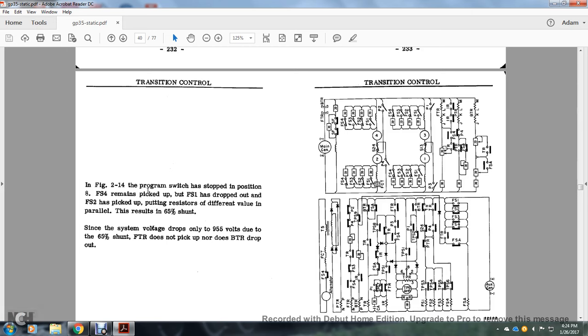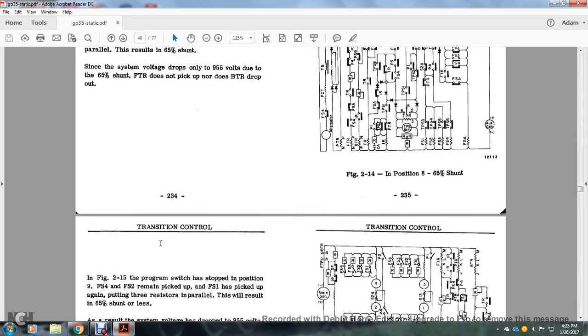Alright, in figure 2-14, the program switch has stopped and field shunt 4 remains picked up. The field shunt 1 is dropped out, and field shunt 2 is picked up, putting in resistors of different value in parallel. The result is 65% shunt. Since the system voltage dropped to 955 volts due to the 65% shunt, the front transistor relay doesn't pick up nor does the back transistor relay drop out.